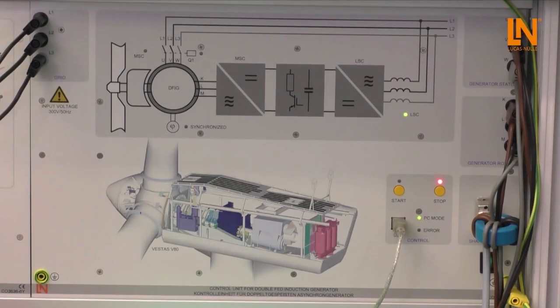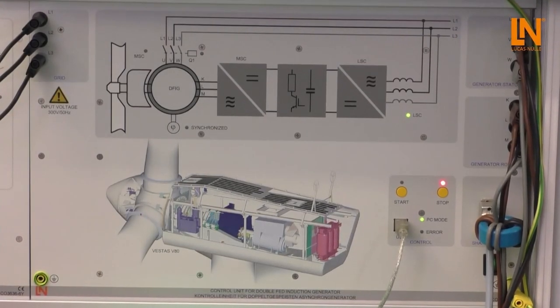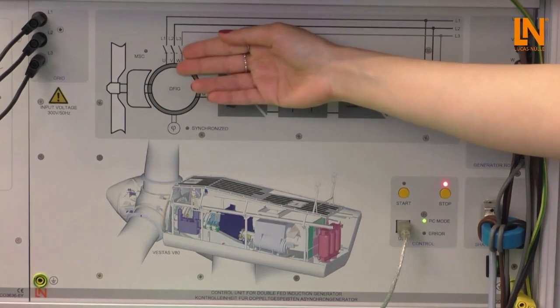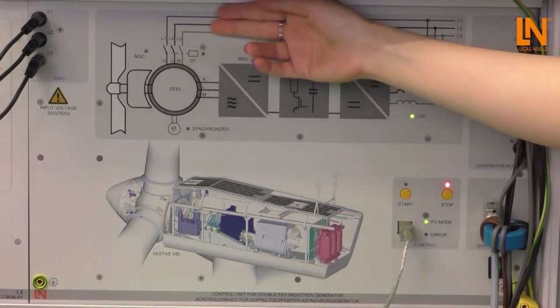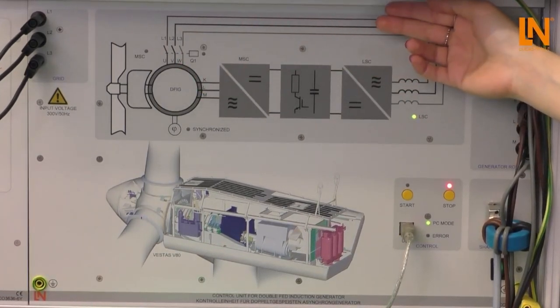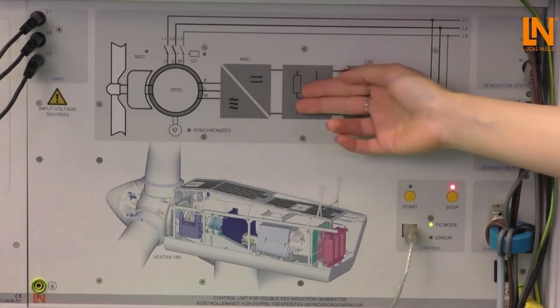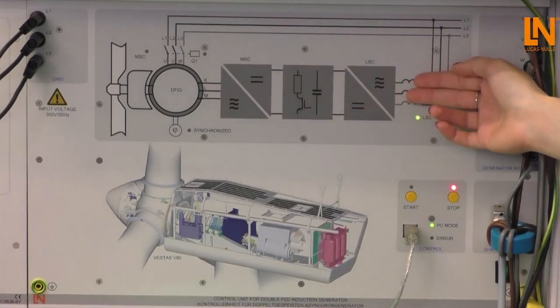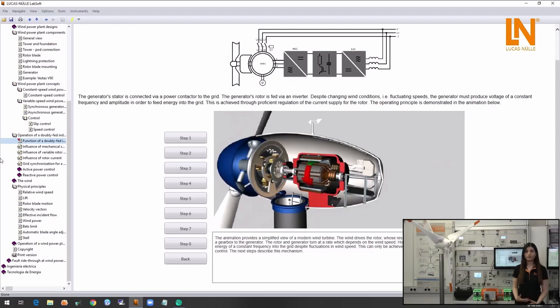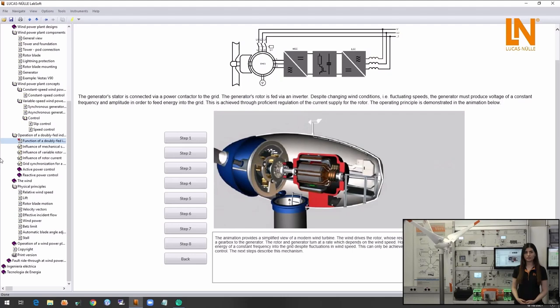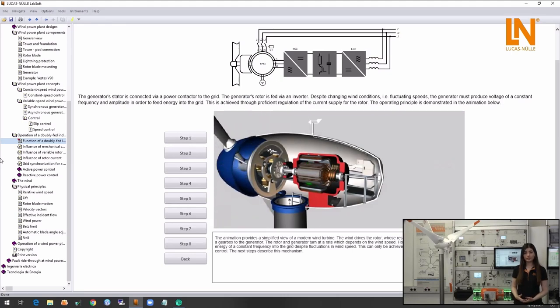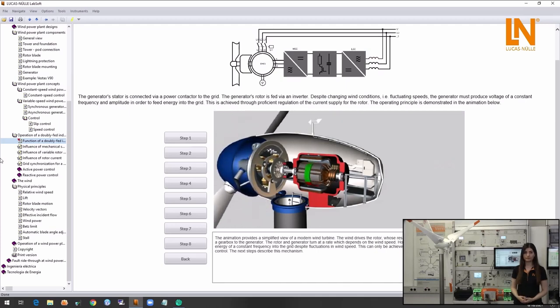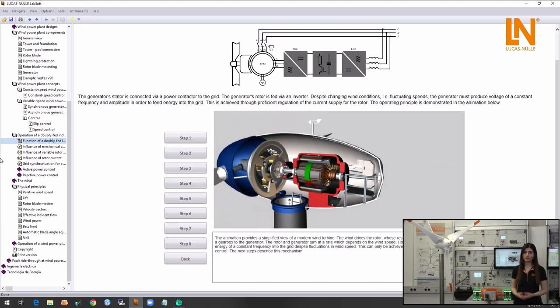First let's take a look at the operation of a double fed induction generator. The stator of this generator is directly connected to the grid and the rotor side is connected through the frequency converter. The fluctuation of wind conditions, the aerodynamic position of the blades and other factors influence the rotor speed of the generator. But the generator must produce the voltage at a constant frequency and amplitude to be fed to the grid. For this the rotor's field will rotate in a way to compensate the variations.